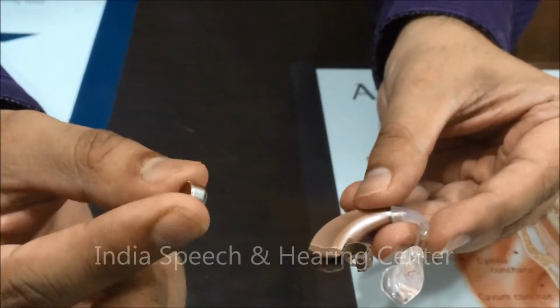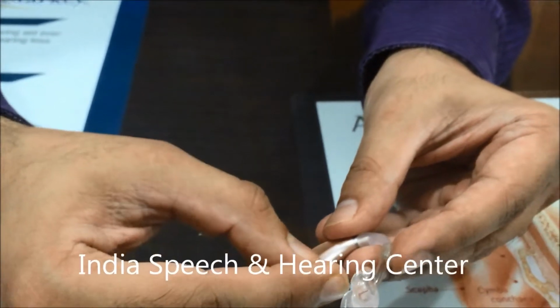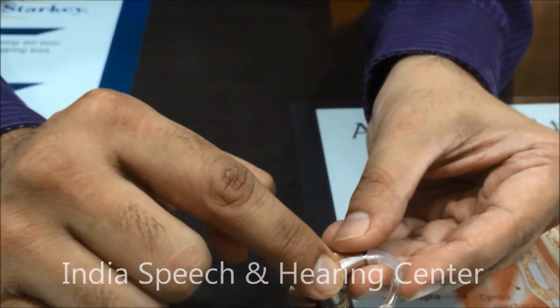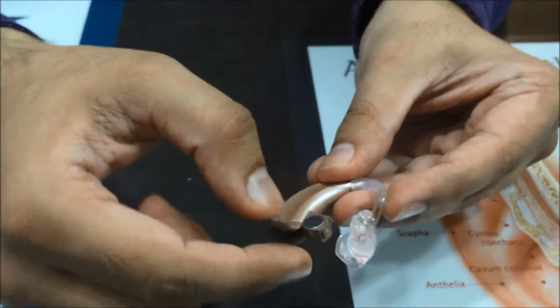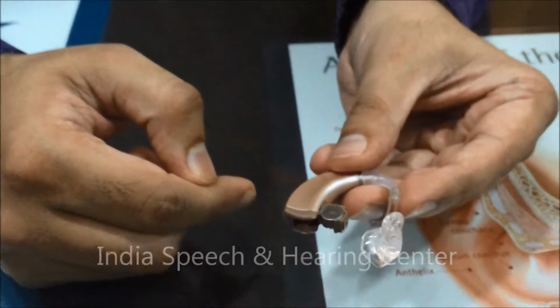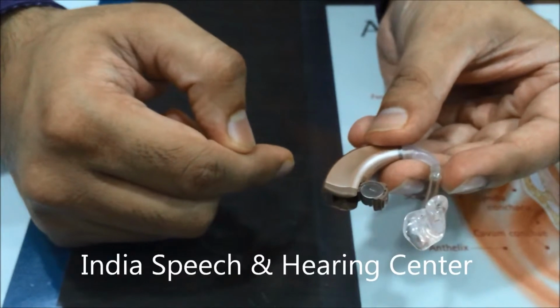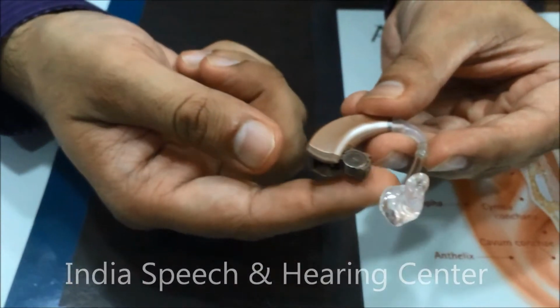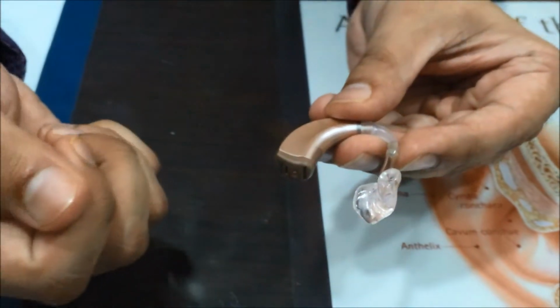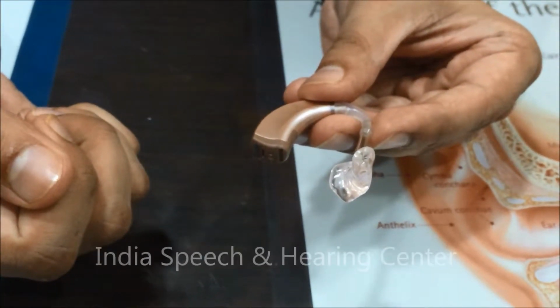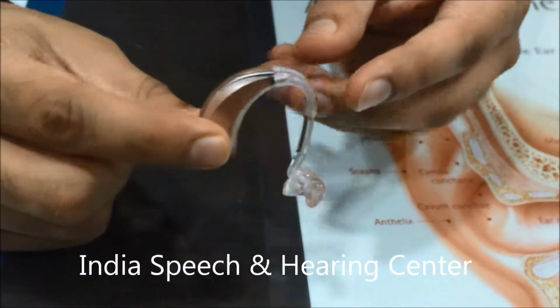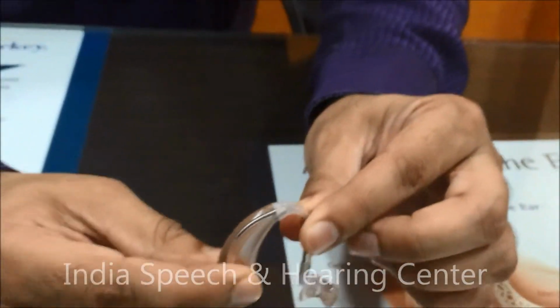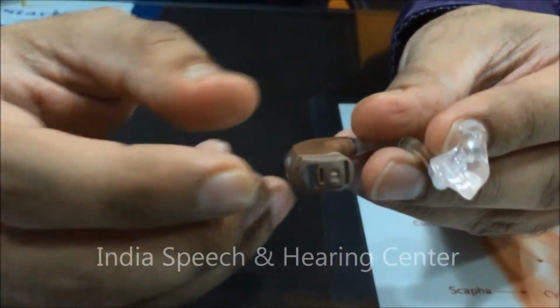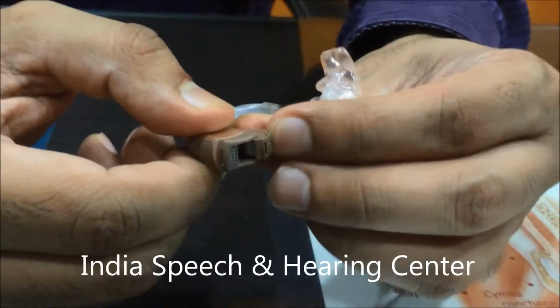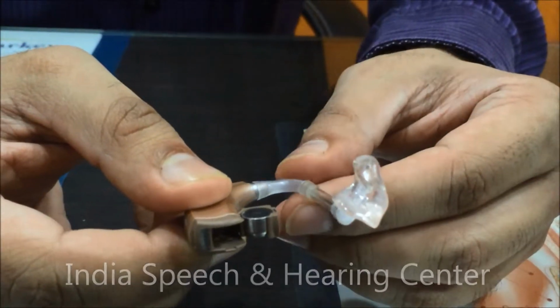You can use your hand to insert the battery from the top and very simply place it in the battery door. This is how the hearing aid battery has to be put. Once the battery door is closed, the hearing aid starts functioning. Typical BTE hearing aids nowadays don't have an on and off switch. So the procedure to switch the hearing aid off and save battery is to keep the battery door open when the hearing aid is not in use.